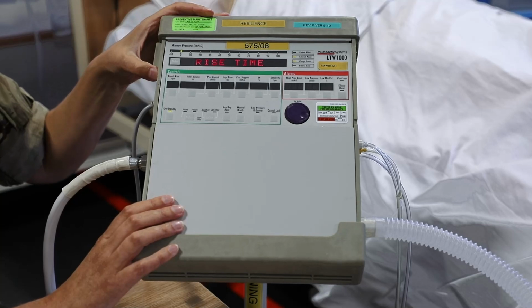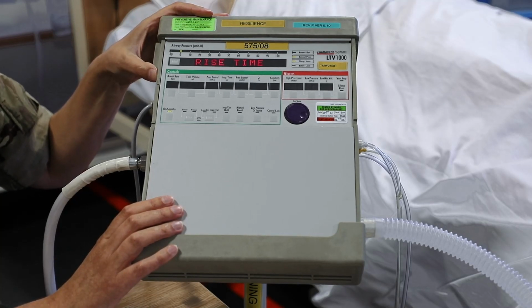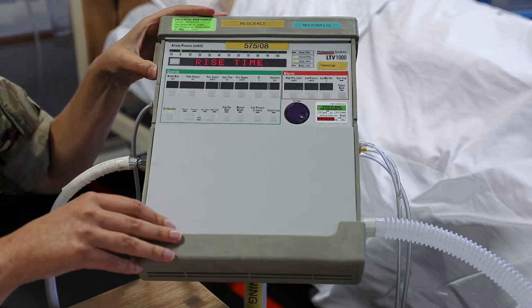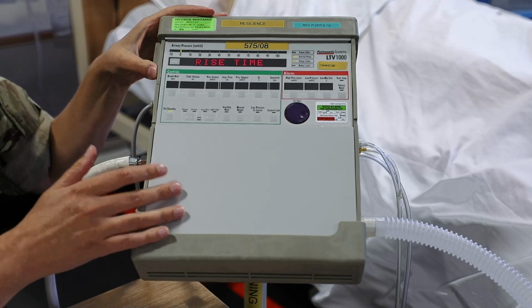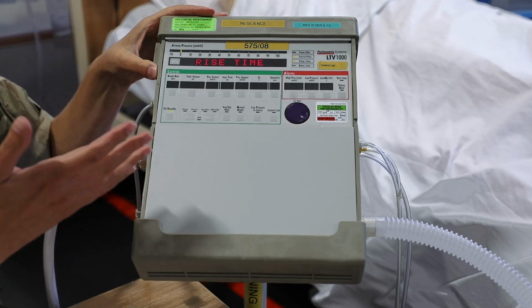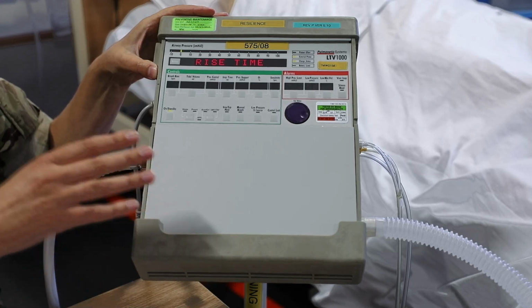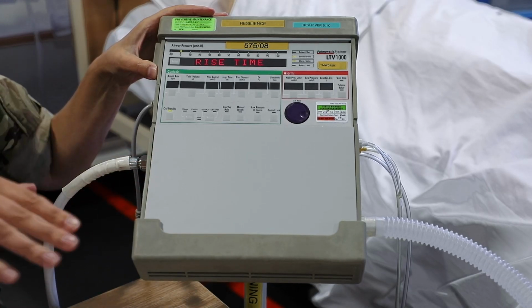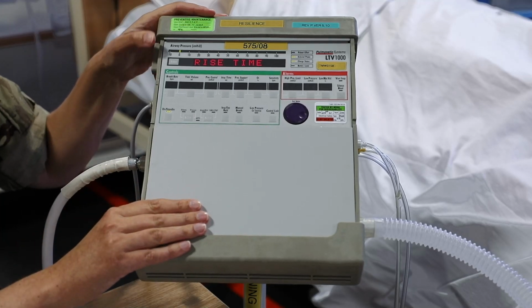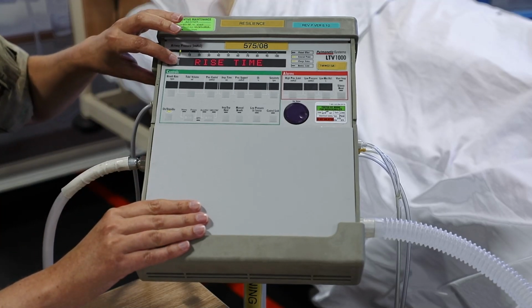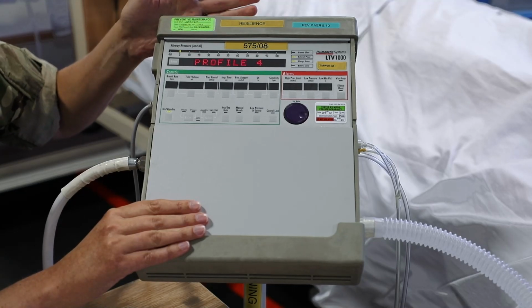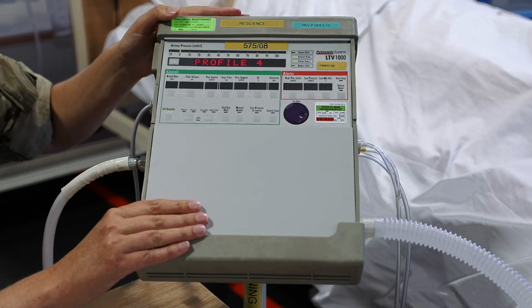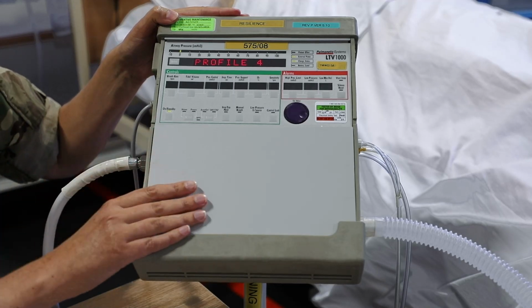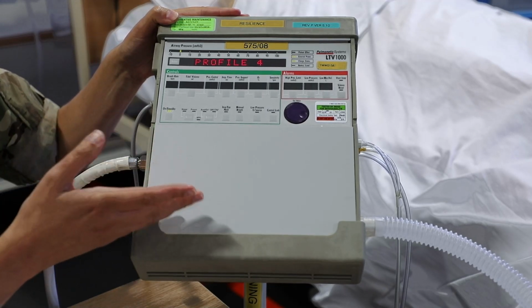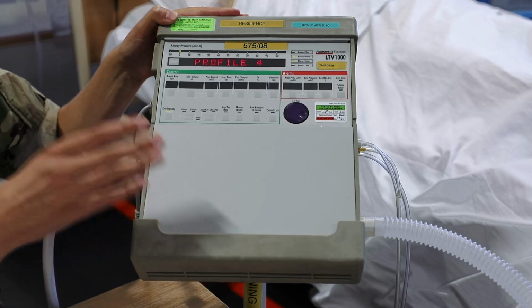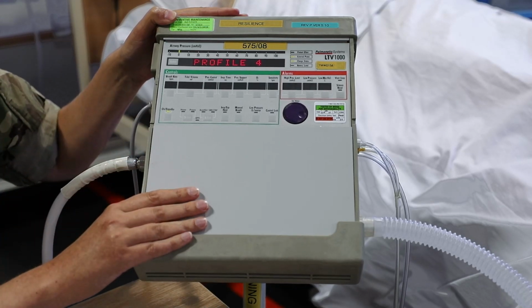Select the menu to go in, and the first option here is our rise time. And the way I remember this is, if you're used to using Draegers, it's a bit like a ramp. It's how gentle you want to deliver the breath. You can either deliver the breath very harshly in and out, or you can give them a much more gentle flow of inspiration and expiration. This is set as standard at profile 4, just because that's the most effective profile that certainly on CCAST we've found, but you can adjust it if you want either a more harsh or a more gentle delivery of the breath.